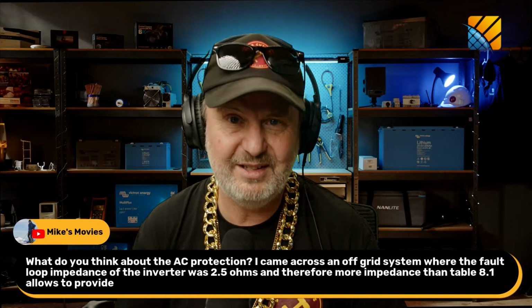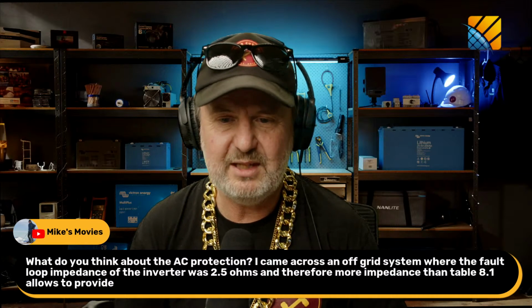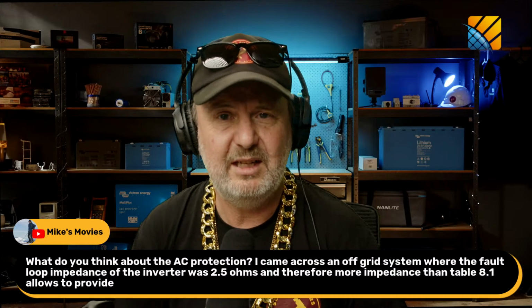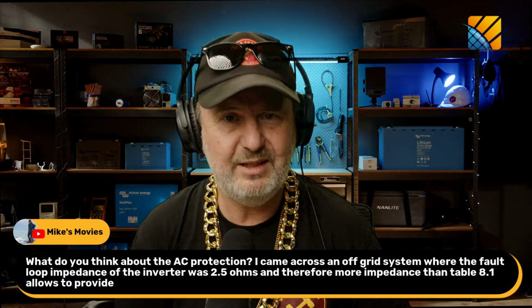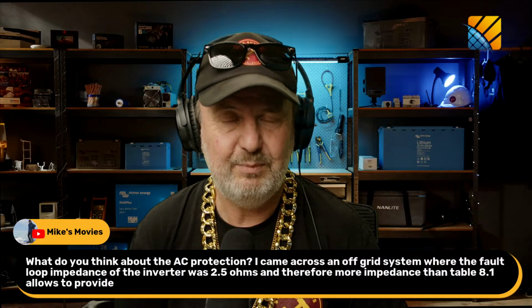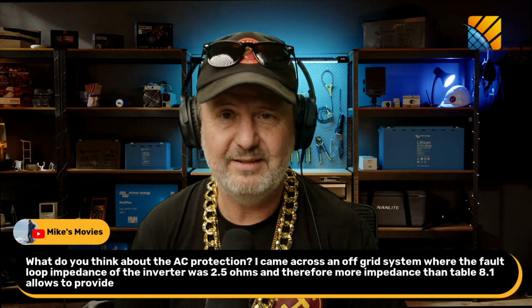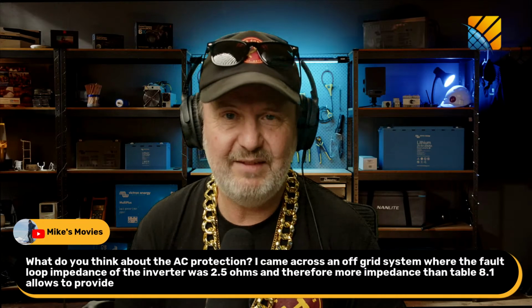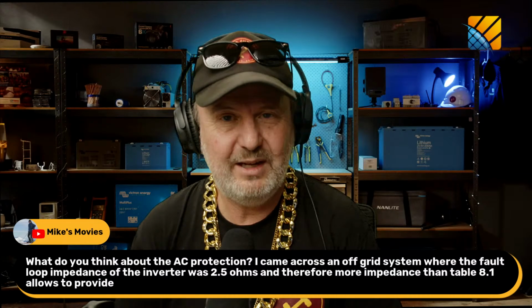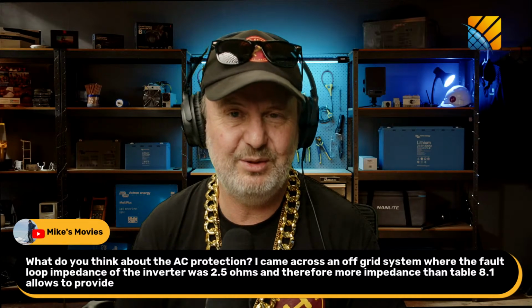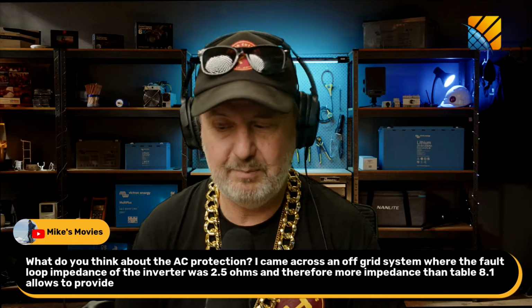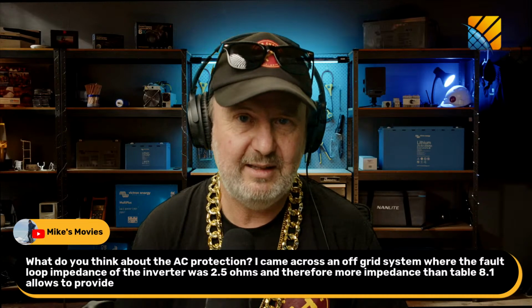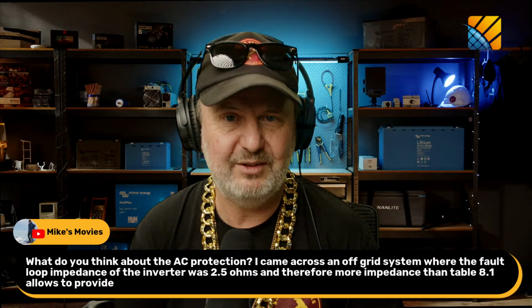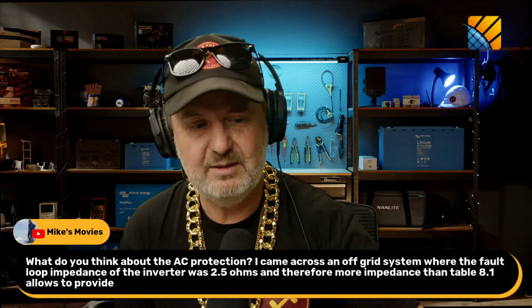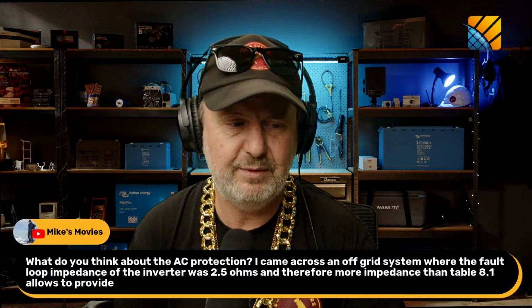Well, it should by design do that. But let's say you've got a very small inverter, a 2 kilowatt inverter. It can only deliver 2 kilowatts, but if you've put a 32 amp circuit breaker on the output, it's never going to trip. So you need to size the protection to suit the maximum inrush that can be provided by the inverter. The fault loop impedance is a bit of an interesting one for off-grid. Thanks for that one, Mike.